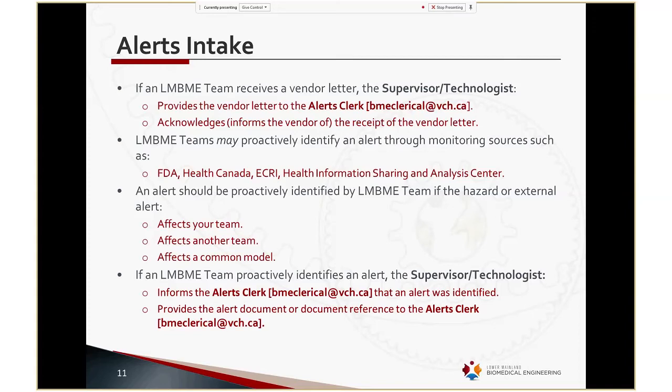Again, in terms of the proactive identification, everybody's more than welcome to monitor for new alerts from sources such as, let's say, FDA, Health Canada, ECRI, the Health Information Sharing and Analysis Center, that's more cybersecurity related alerts. And so again, if you see an alert out there and it's related to something that might affect your team, you think it might affect another team or affect a common model that's serviced, please do identify that alert and send it into the alerts clerk.